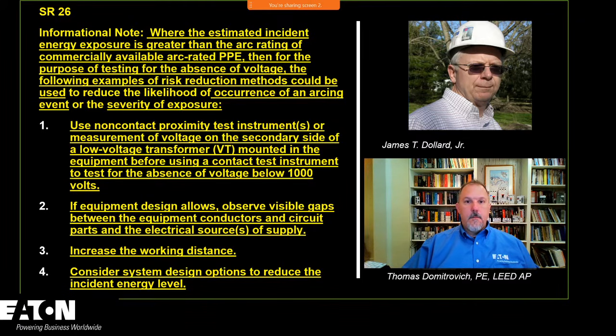So if an individual had a situation like that, they could use a non-contact proximity tester, and they could use it on a pole. So you could get a 12, 15-foot pole, put a non-contact proximity test instrument. You're using distance as a tool, and you're isolating yourself. Or in number one, there you could have permanently mounted test equipment, and we actually permit that now in 120.5. The second option is where the equipment allows us to see a visible gap.